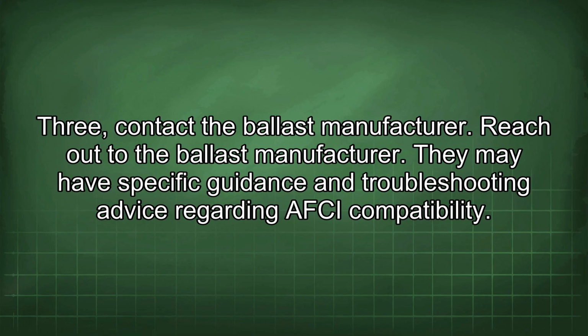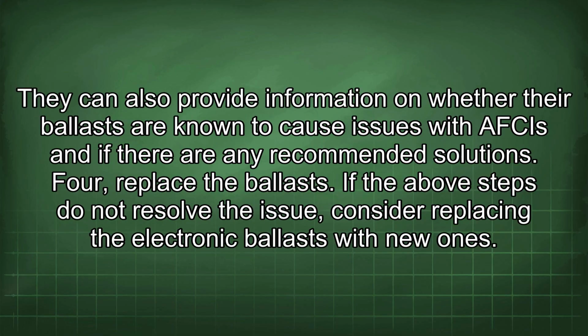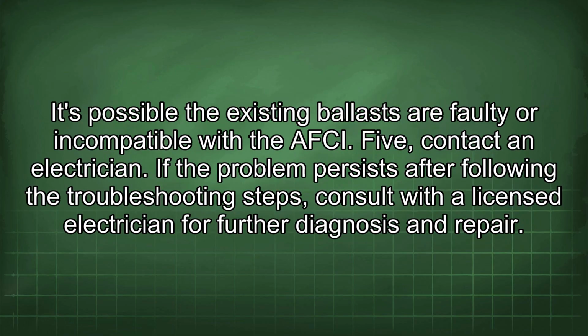3. Contact the ballast manufacturer. Reach out to the ballast manufacturer. They may have specific guidance and troubleshooting advice regarding AFCI compatibility. They can also provide information on whether their ballasts are known to cause issues with AFCIs and if there are any recommended solutions. 4. Replace the ballasts. If the above steps do not resolve the issue, consider replacing the electronic ballasts with new ones. It's possible the existing ballasts are faulty or incompatible with the AFCI.